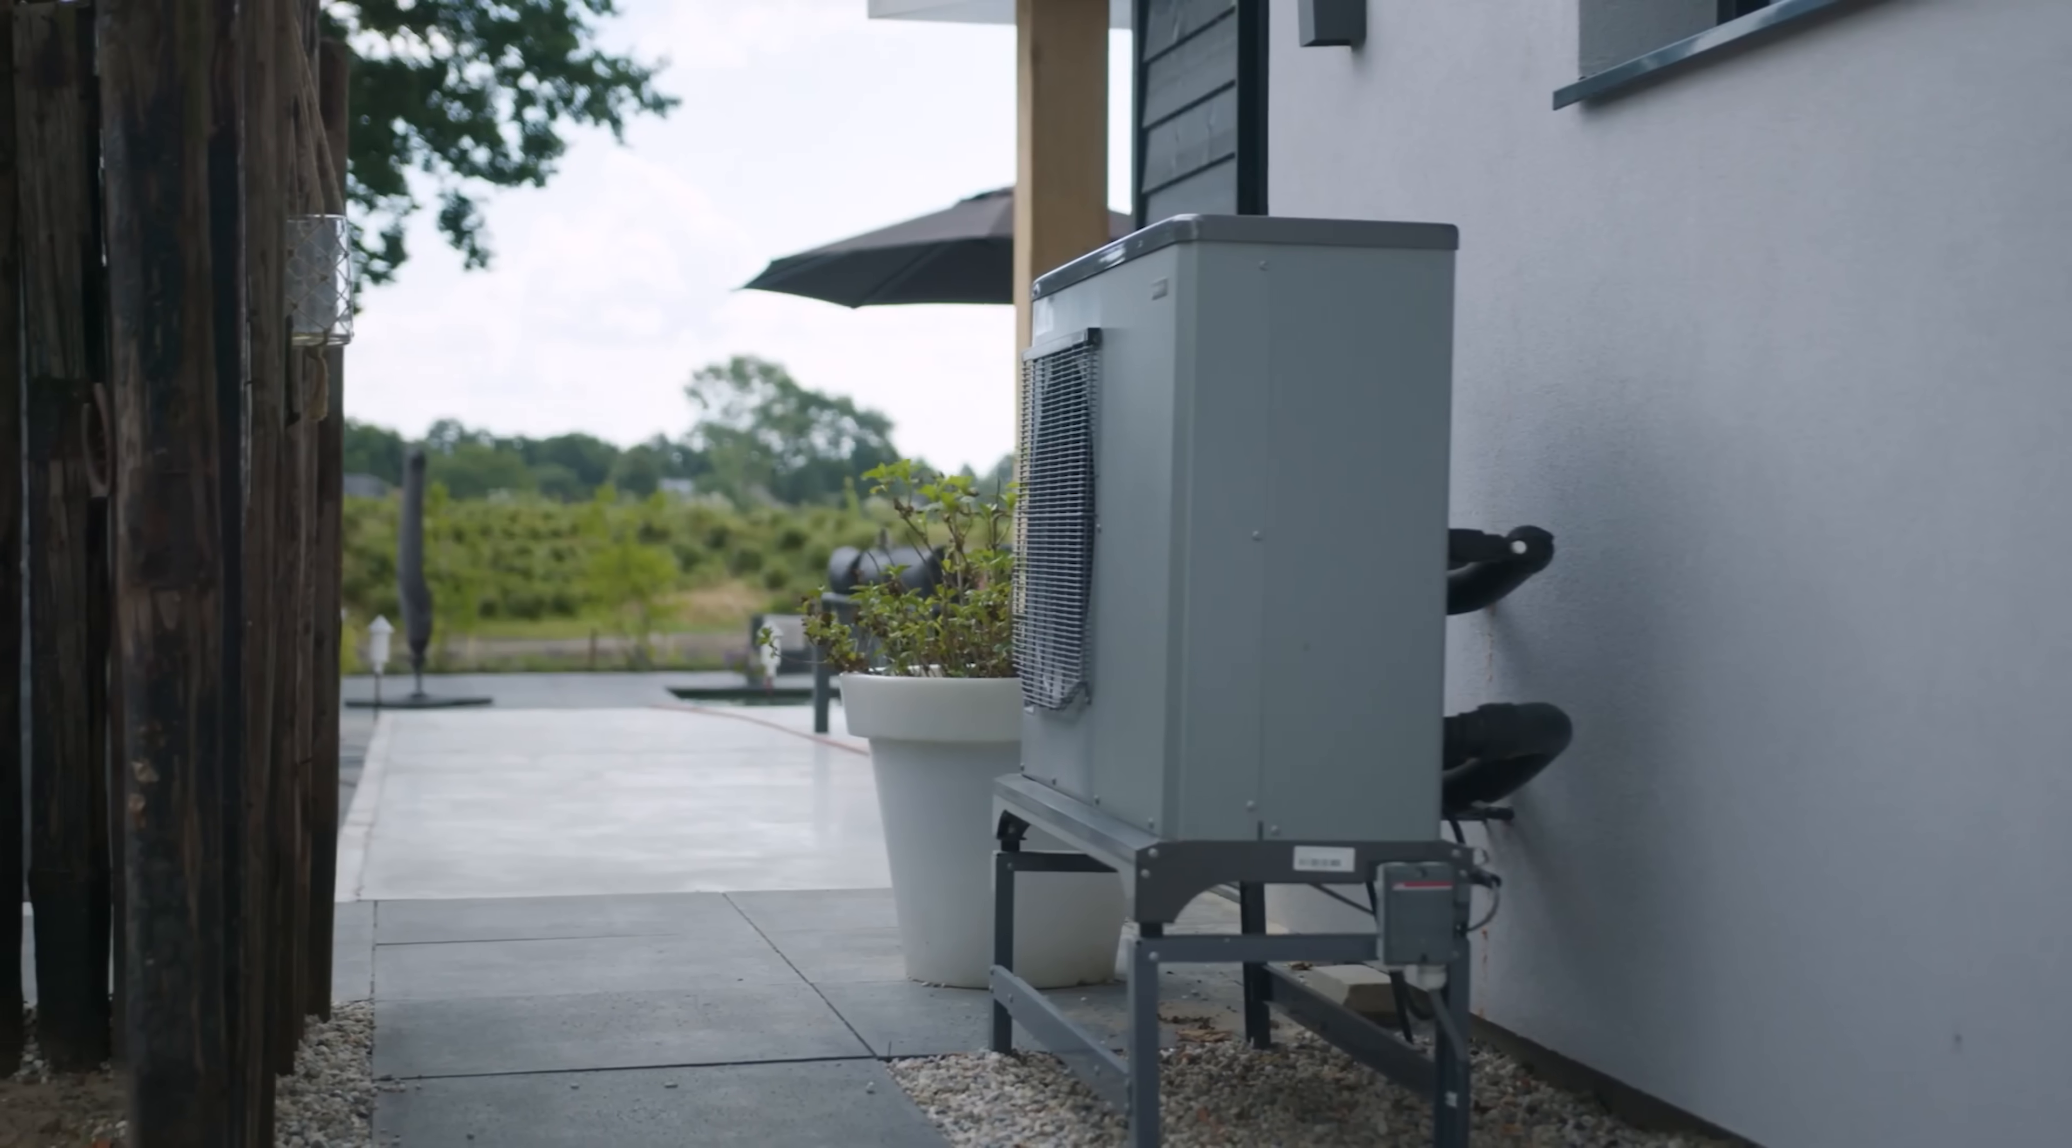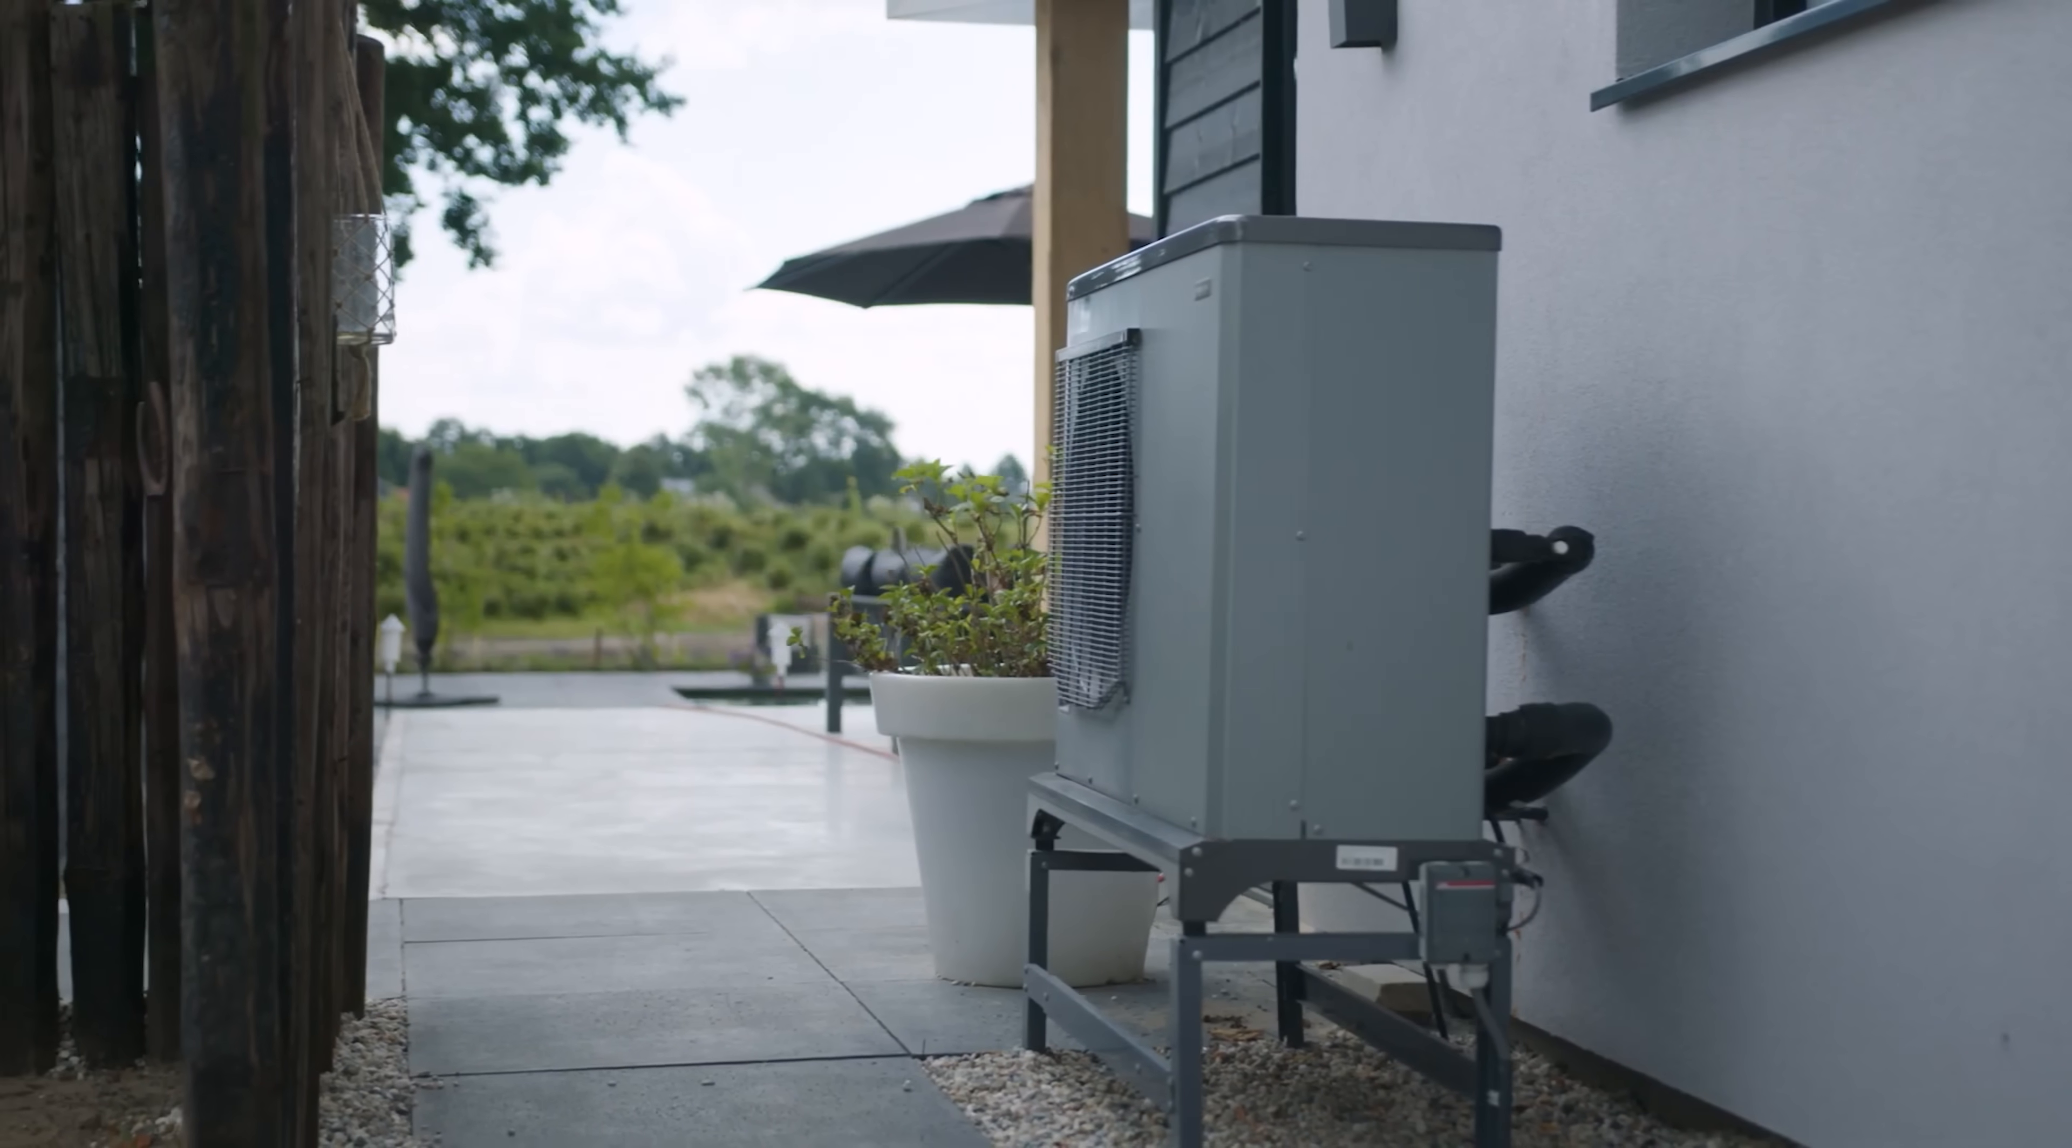And so when you have a heating only system, you really only need like a boiler to generate hot water. But when you do heating and cooling, ideally you have a unit that can provide hot and cold water. And that would be an air to water heat pump, like I mentioned earlier. And those are highly efficient and can also use renewable energy sources, which is great. There's air to water heat pumps. There's also geothermal heat pumps. But either way, you're using those to generate hot or cold water. And those are what we call the energy source because those are generating the hot or cold water. Those are heating up or cooling down that water.